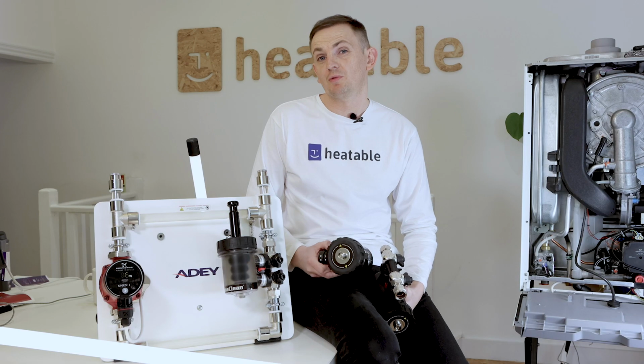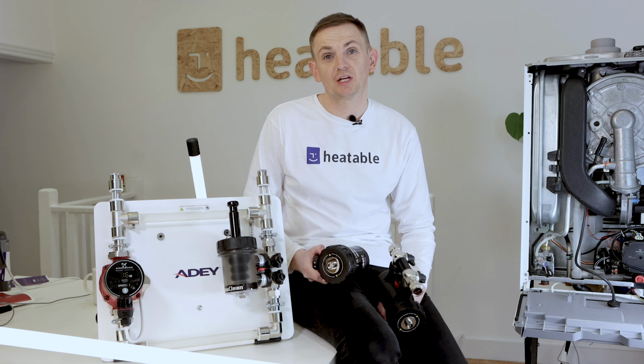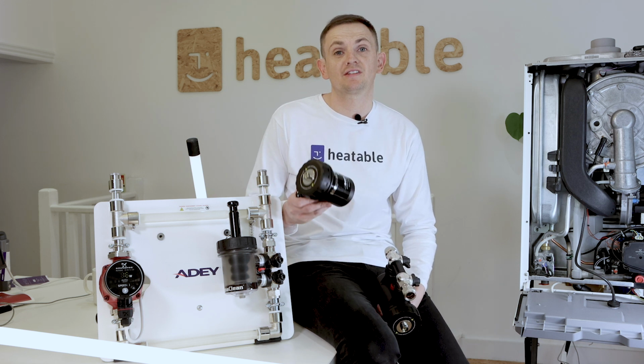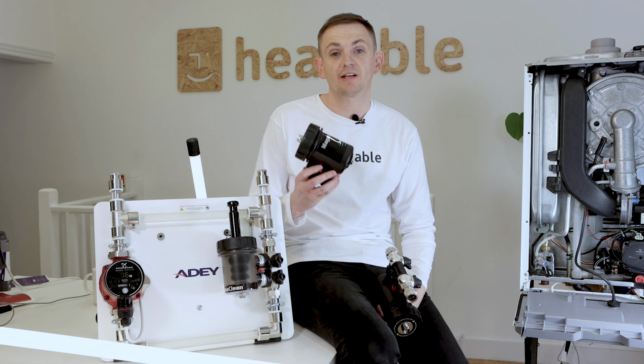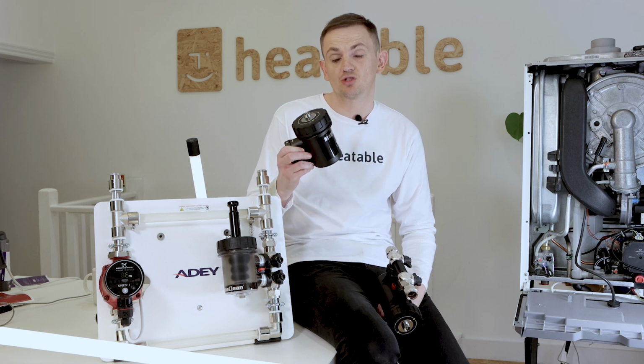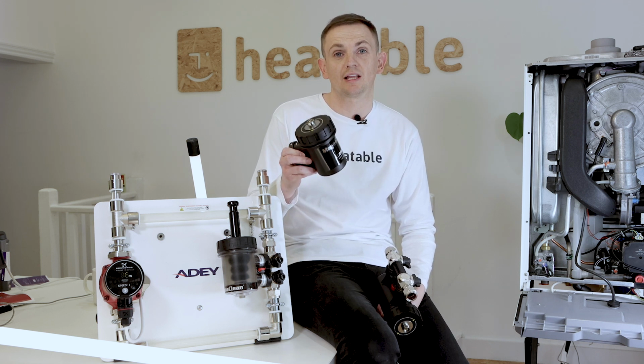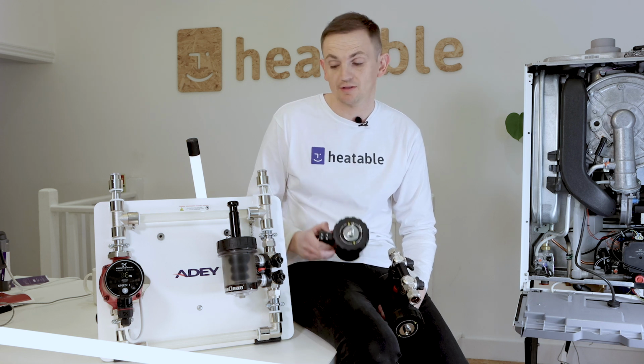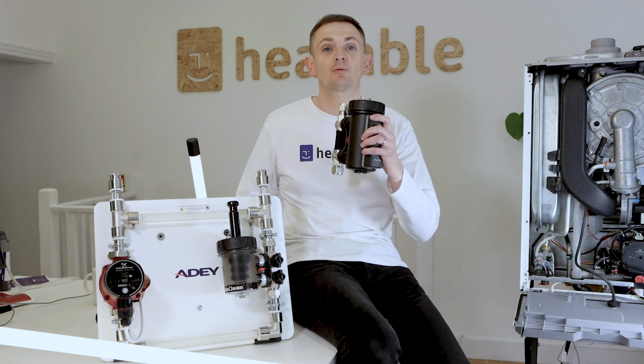So it's not actually a requirement to fit a filter with a boiler, but Heatable does. If another fitter fits a filter with their boiler, they may include something like this. This is a smaller filter which captures much less magnetite than the one that Heatable fits. Heatable will install the ADEY Pro 3.